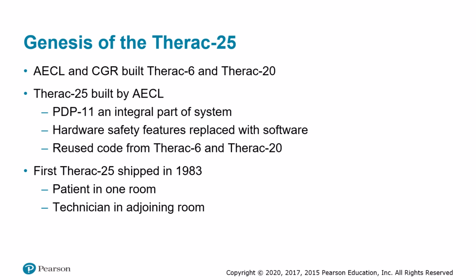Like the Therac-6 and the Therac-20, the Therac-25 made use of a PDP-11. But unlike its predecessor machines, AECL designed the PDP-11 to be an integral part of the device. The linear accelerator was incapable of operating without the computer, actually. So this design decision enabled AECL to reduce costs by replacing some of the hardware safety features of the Therac-20 with software safety features in the Therac-25.